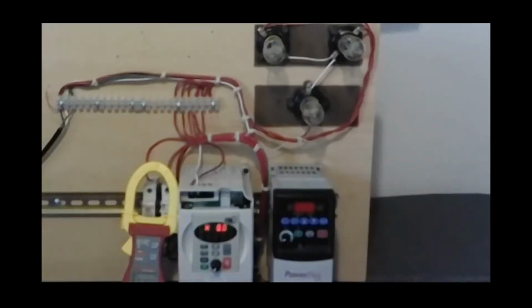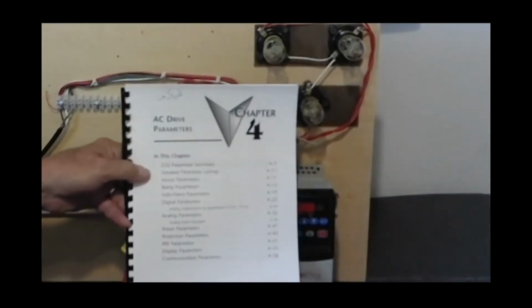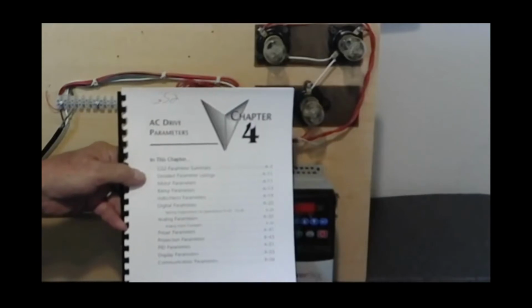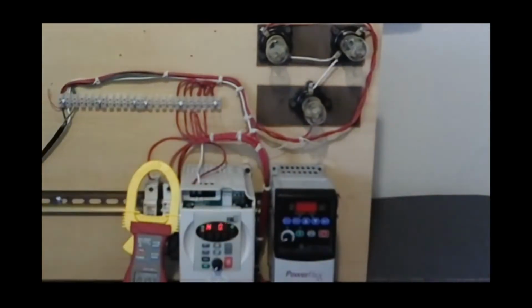Now, troubleshooting these drives can be a little bit different. We can troubleshoot the mechanical aspect and the electronic aspects, but the best friend you'll ever see with your drive is the manual that came with it. Every one of the drives is going to have error codes, and every error code will be different for every make and model of drive. There is no standardization of error codes.